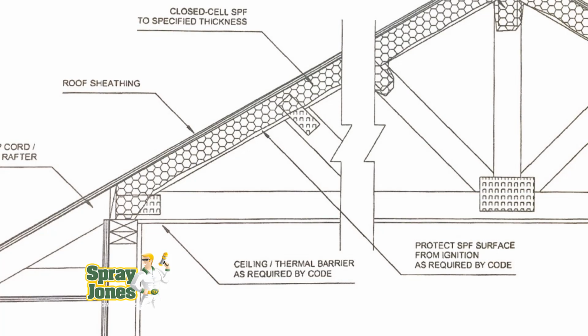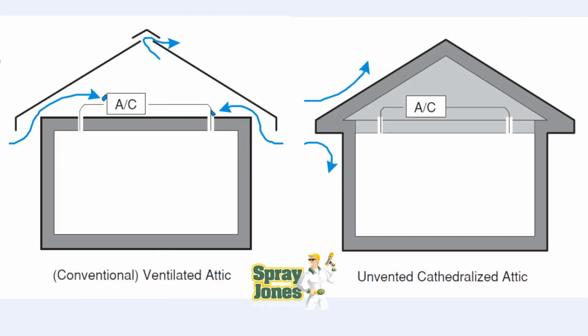But what I get clients to do is if there's going to be an area for the mechanical equipment, we get them to compartmentalize that, build a little room up in the attic with a floor and walls and a roof. And we have that gyprocked or paneled or what have you to create the thermal barrier. And then we have rough openings cut, ductwork put through it, return airs, supply, everything comes in and out. Carbon monoxide detector, smoke detector, all of the detectors are in place, and then all of the penetrations through the walls are resealed up with can foam and what have you.